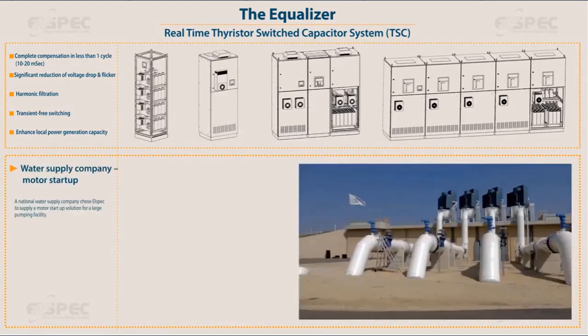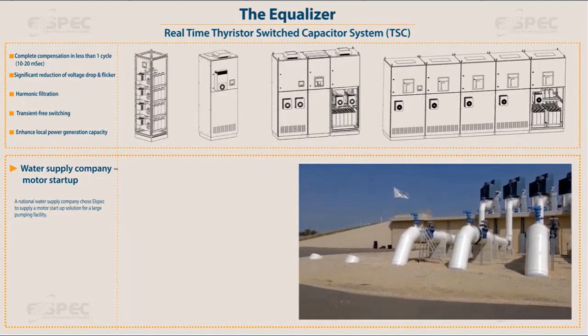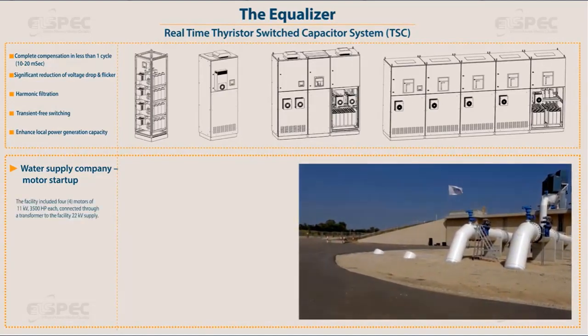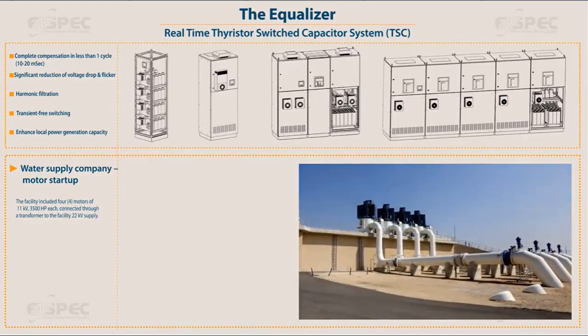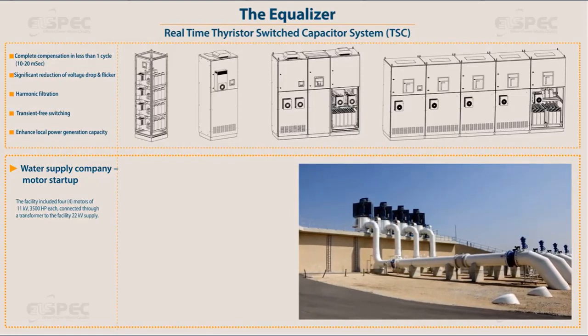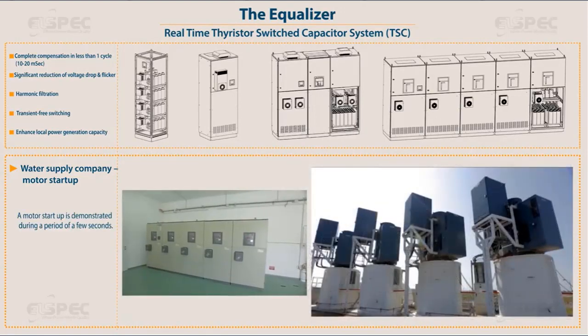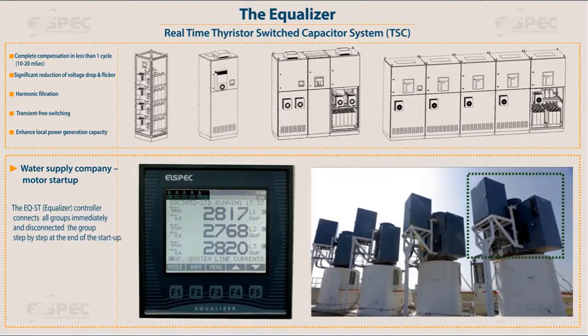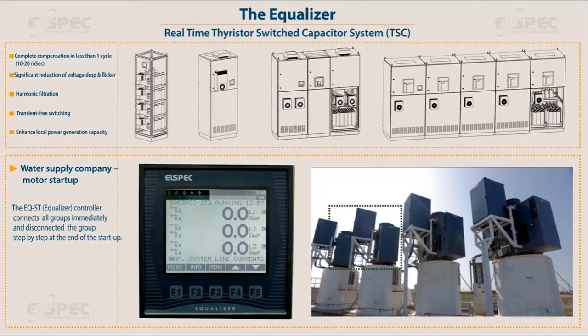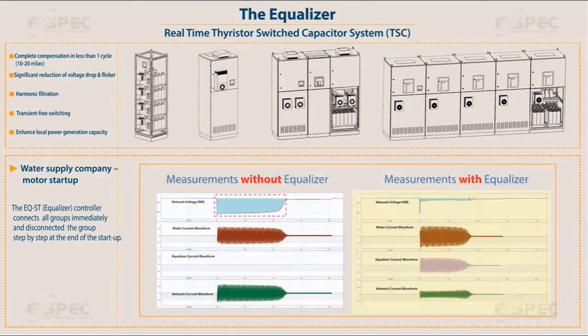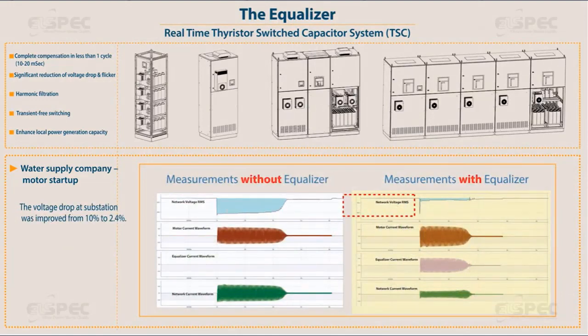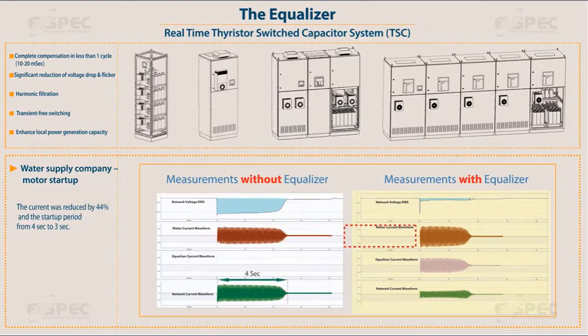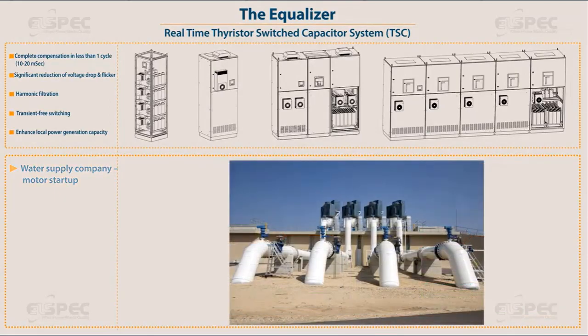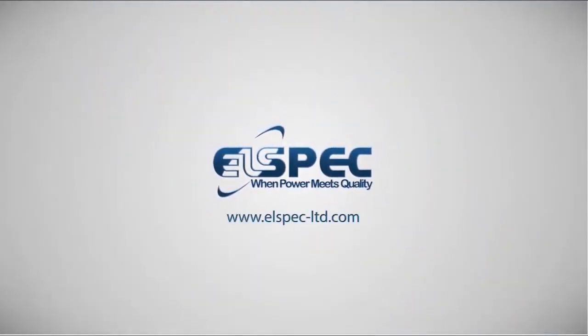A national water supply company chose ELSPEC to supply a motor startup solution for a large pumping facility. The facility included four motors of 11 kV, 3,500 HP each, connected through a transformer to the facility 22 kV supply. A motor startup is demonstrated during a period of a few seconds. The EQST equalizer controller connects all groups immediately and disconnects the groups step by step at the end of the startup. The voltage drop at the substation was improved from 10% to 2.4%. The current was reduced by 44% and the startup period from 4 seconds to 3 seconds. ELSPEC, when power meets quality.